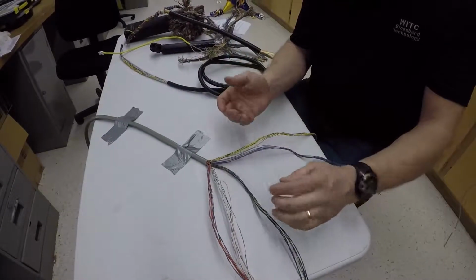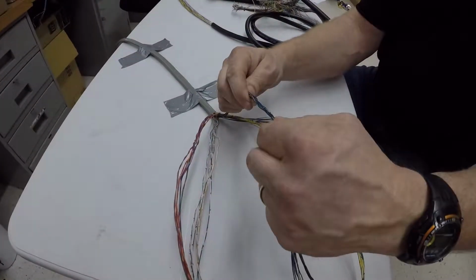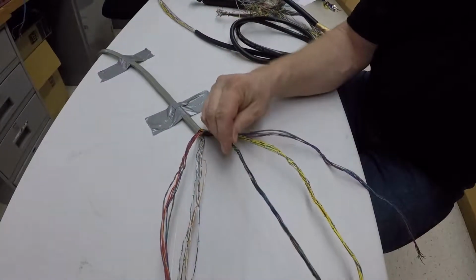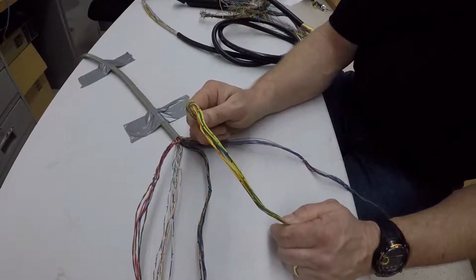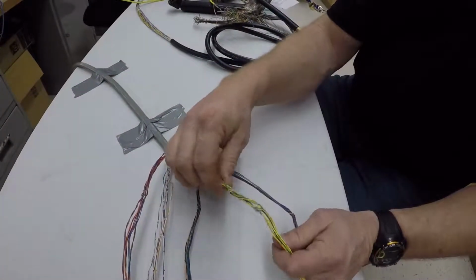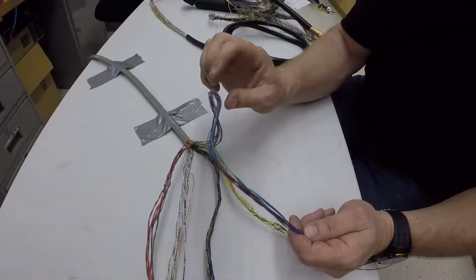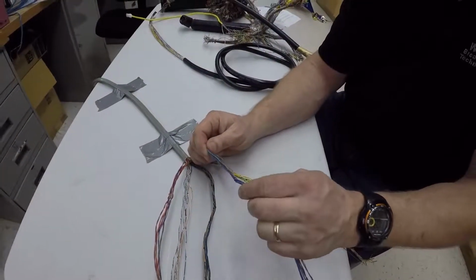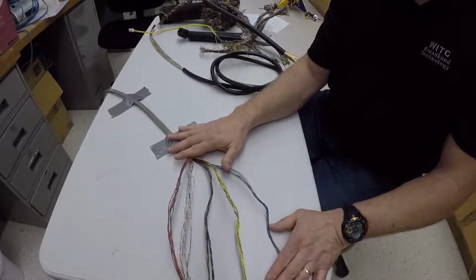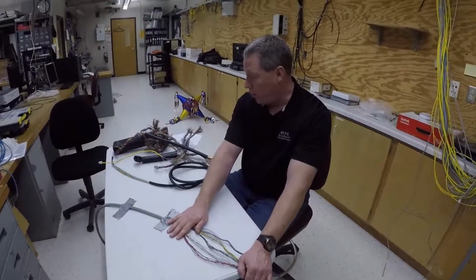Now we can go through all these, but in your documentation you can see the next 5 would be your black series: black, blue, black, orange, black, green, black, brown, and black, slate. And then you would go to your yellows: yellow, blue, yellow, orange, yellow, green, yellow, brown, yellow, slate, and then finally ending up that would be up to 20, and then 21 would be your violet. It's not purple, it's violet, blue, violet, orange, violet, green, violet, brown, and violet, slate. That is your 25 pair color code. That's our industry standard, and that's how we identify all our colors in our cables.